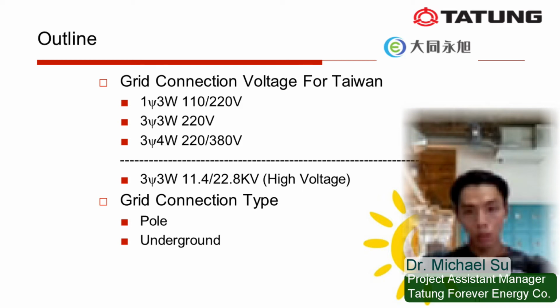So, generally speaking, there are actually 4 wires in the 3-wire one and 5 wires in the 4-wire one, for your information. When it comes to even higher voltage, here in Taiwan we commonly have the 11.4 or the 22.8 kilovolt equipment. Usually the transformers on the poles are the 11.4 kilovolt ones, and the 22.8 kilovolt systems are usually hidden beneath the ground. In other countries, they might be only 11 or up to 33 kilovolts, depending on the setting. And about the grid connection types, both low and high voltage cables can be divided into two, going on poles or underground.